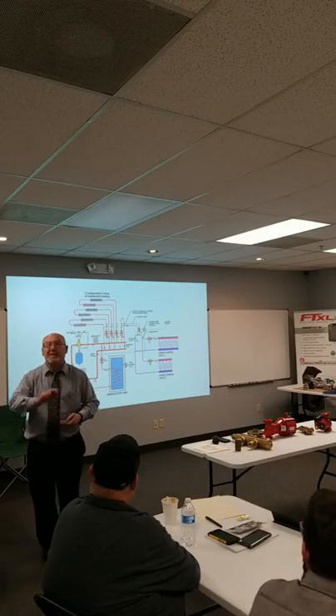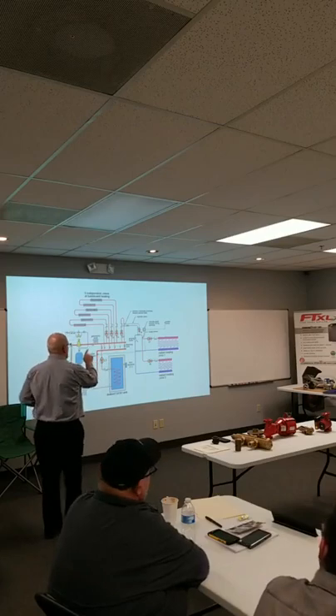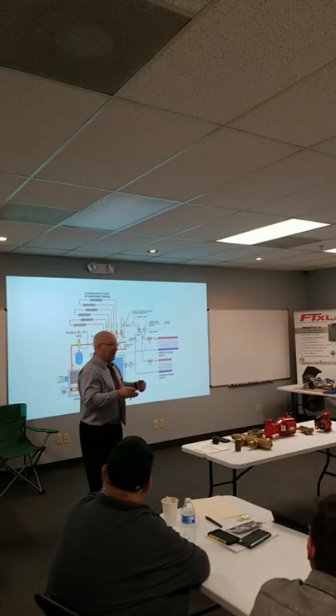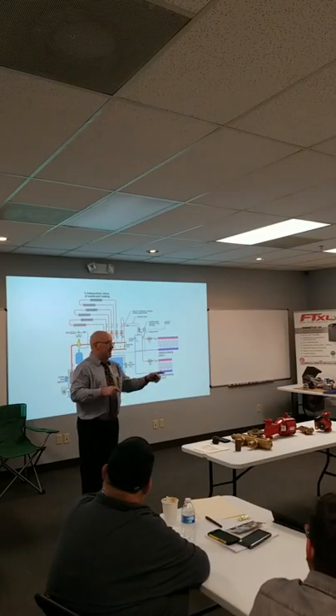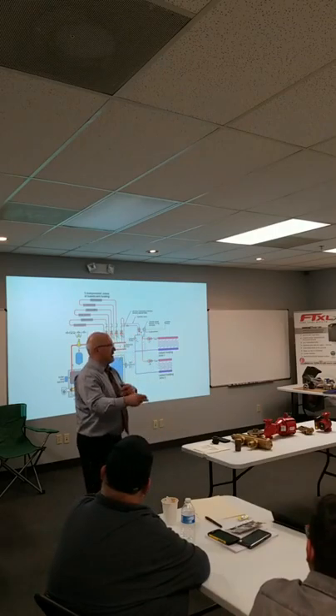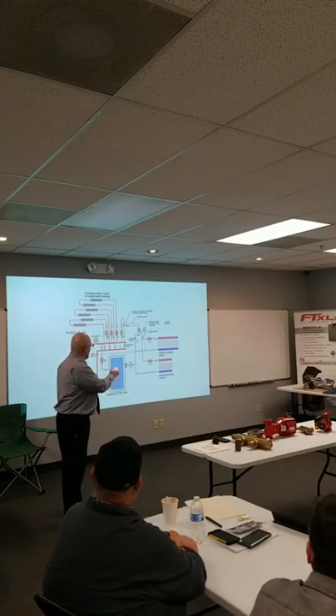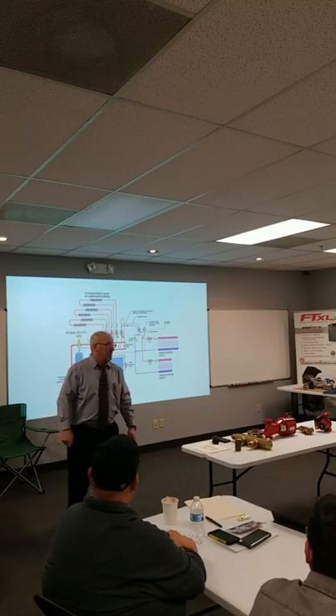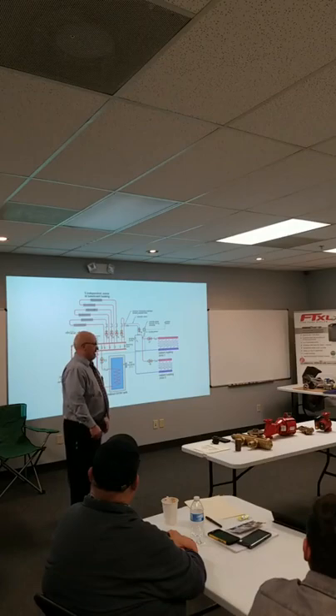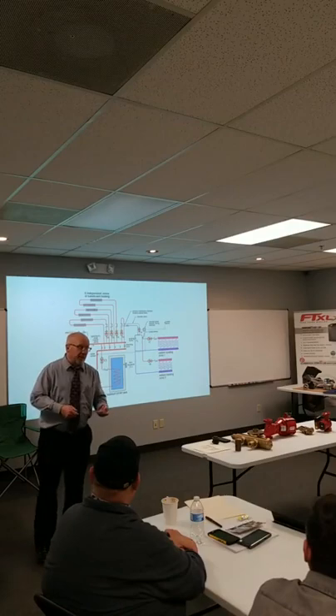I'm sorry, it's getting scratchy. What kind of variable speed pump is that? Is that a cartridge pump? This happened to be a variable speed tekmar injection control, just a little wet rotor circulator. It's just varying voltage to vary the speed? Yeah, it's kind of pulsing the voltage, slowing it down and speeding it up, based on a sensor telling it, I want this water temperature, compared to the outdoor sensor. You can't just change voltage, you have to change frequency. Yes. So injection pumping is a neat way. We can do that with water.